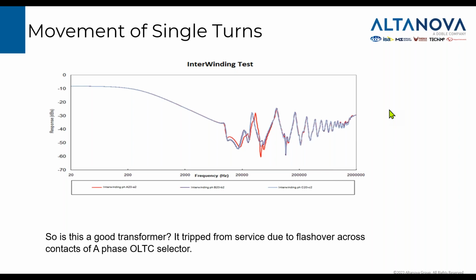And we also did interwinding tests, which are kind of ratio tests made with the SFRA instrument. You can read about it in one of these documents from CIGRE, which I mentioned before. But again, phase A was different. So we started investigating further. The transformer was still drained of oil. There were a few hatches available, including that one of the selector.